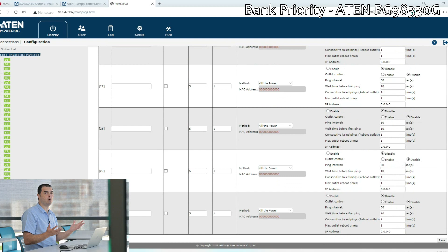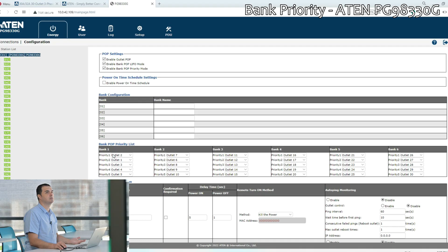We also have here in the upper part, priority. Bank priority means that if you have high consumers, if some of your servers are high consumers and it exceeds the total capacity of our PDU, the product can shut down some of the outlets in order to preserve energy for the servers that need it most. This is your chance to tell the PDU which of your outlets are very important and should not be killed, and which are not. The priority is very simple: the servers that you put at the back don't have any priority. These would be shut down first.